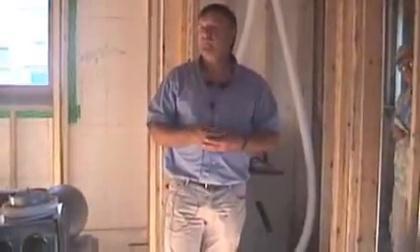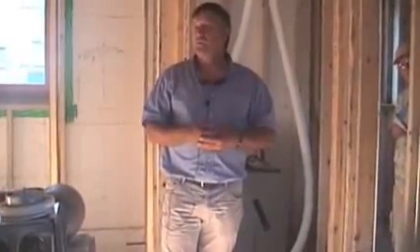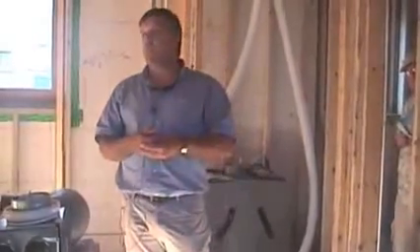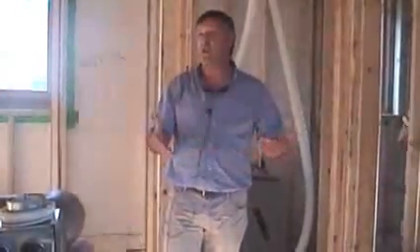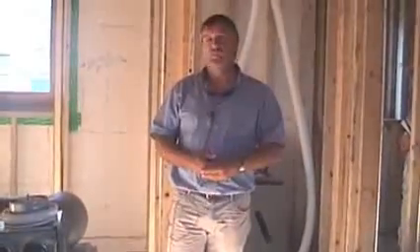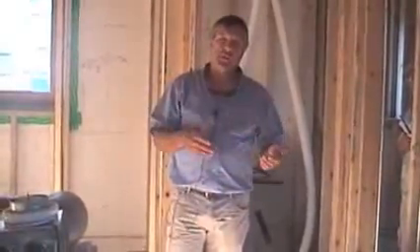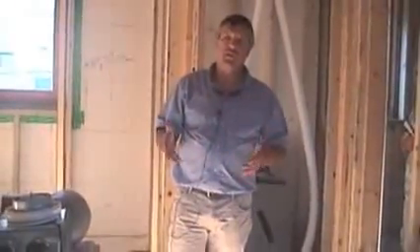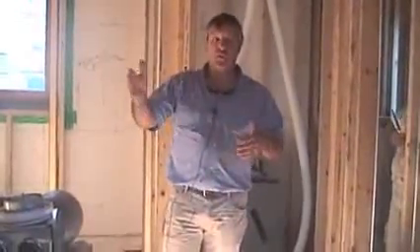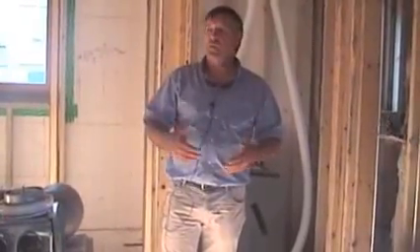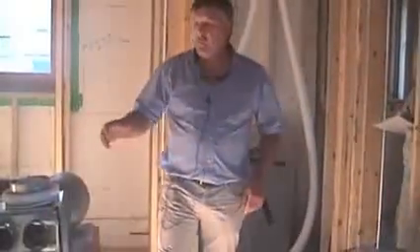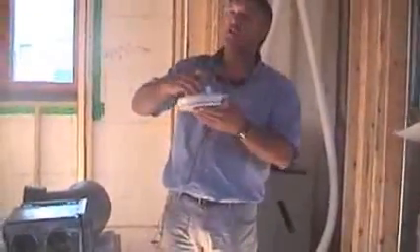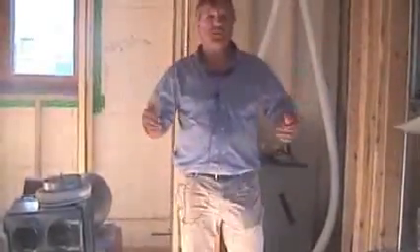Is that something you should check every couple of years, just keep making sure it's there? From our experience, and we have a lot more experience in Europe over much greater time, it isn't an issue. No. And one thing is the ECM motors that we're using are very consistent and don't change. There are some cheaper motors that lose some of their efficiency and so forth over time, but we haven't seen that at all. So it's set, and if people mess around with these, you may have an issue with that a little bit, but it's not going to be enough to change the balance of the system.